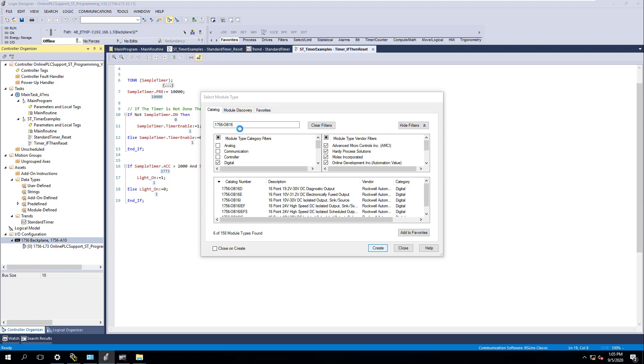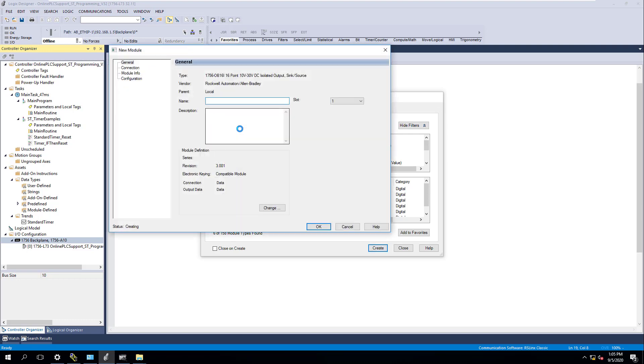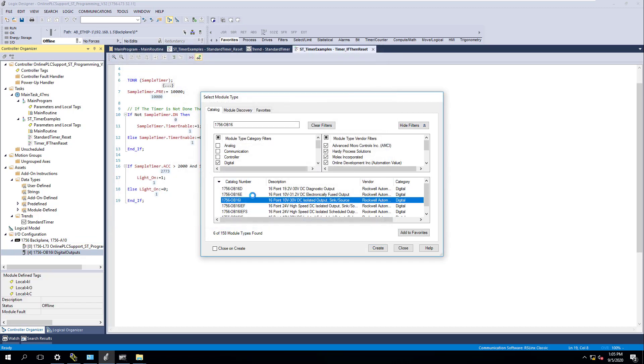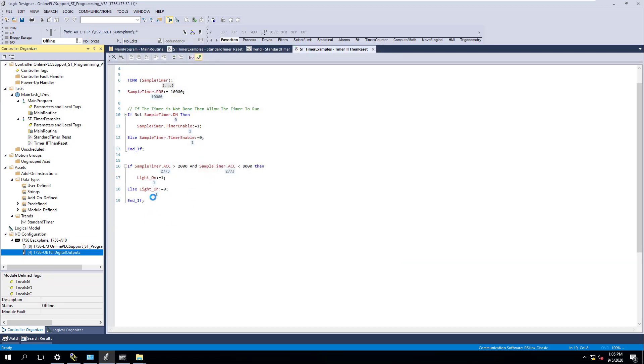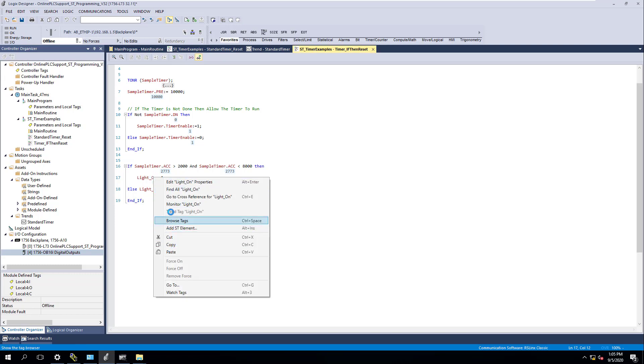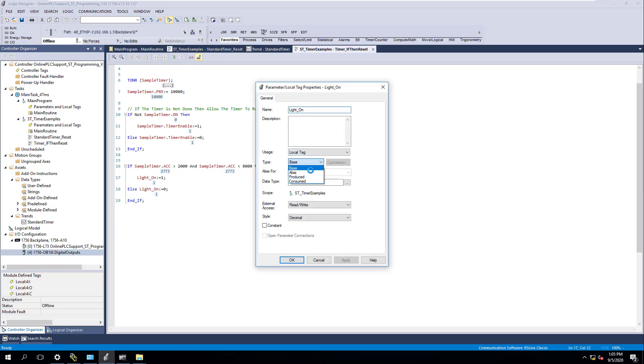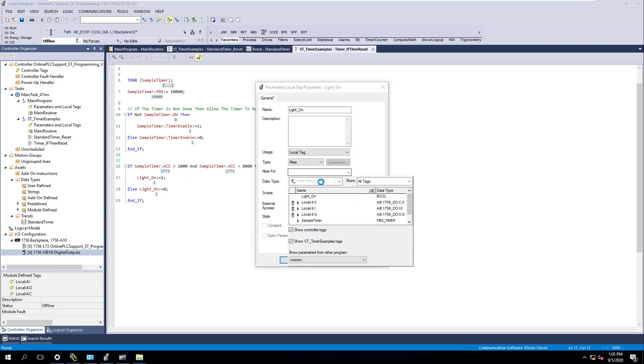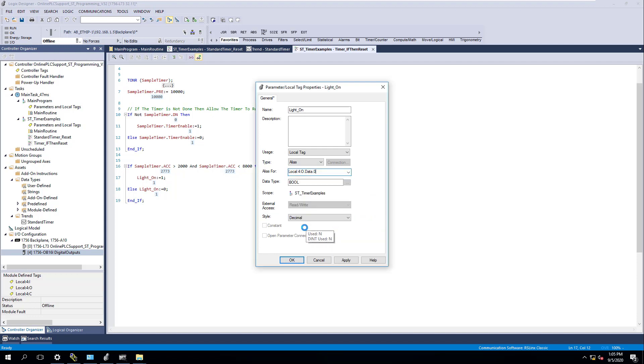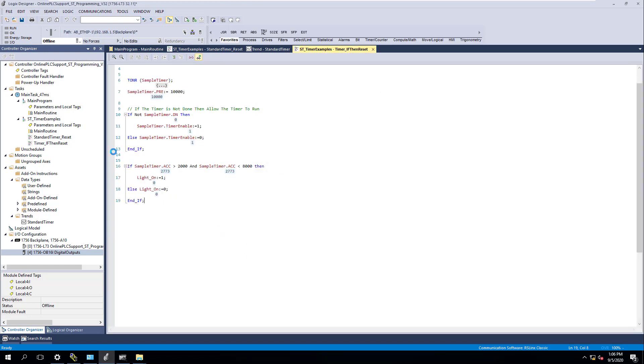You can come in and use this stuff based upon looking through your RSLinx if you already have it set up. We'll call this Digital Outputs. This is in slot 4. We're going to click OK. We're going to close that out. And then what we're going to do is change this tag to match one of our lights. Now we're going to edit it. We're going to come back in here, change this to an alias. We're going to come down here and get the output. We're going to change this to output zero.